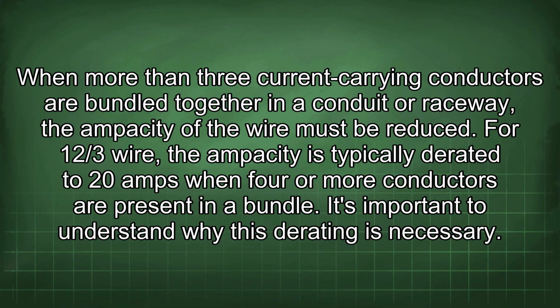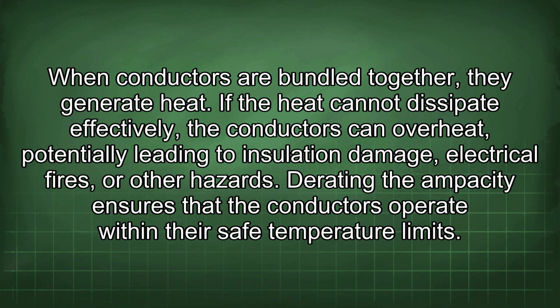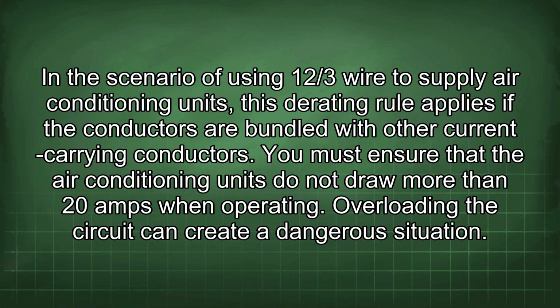It's important to understand why this derating is necessary. When conductors are bundled together, they generate heat. If the heat cannot dissipate effectively, the conductors can overheat, potentially leading to insulation damage, electrical fires, or other hazards. Derating the ampacity ensures that the conductors operate within their safe temperature limits. In the scenario of using 12/3 wire to supply air conditioning units, this derating rule applies if the conductors are bundled with other current-carrying conductors.